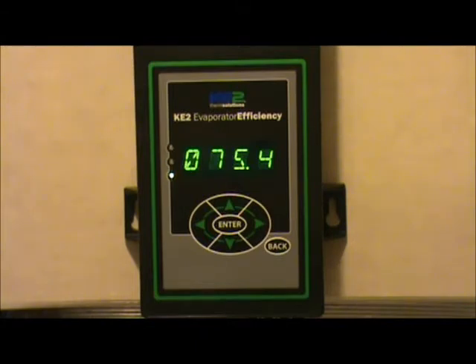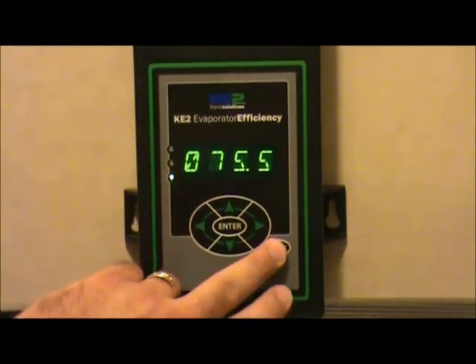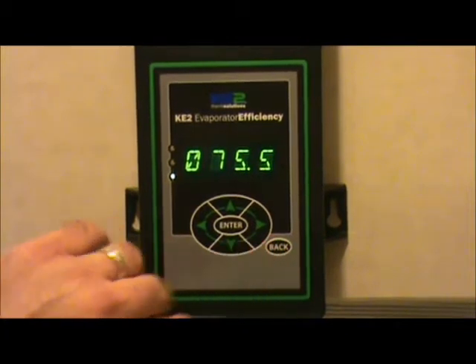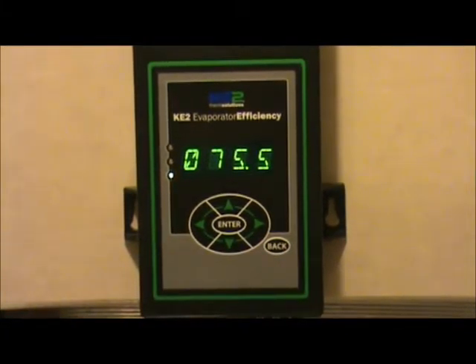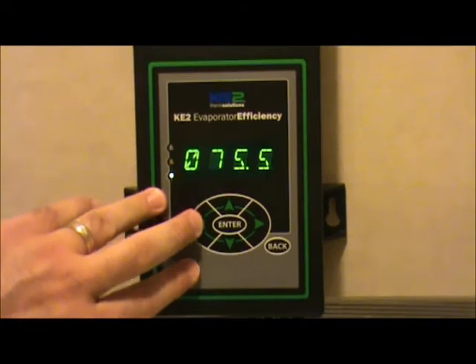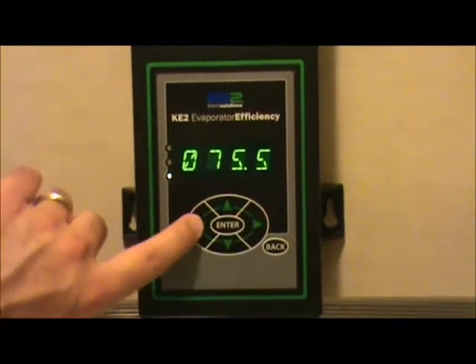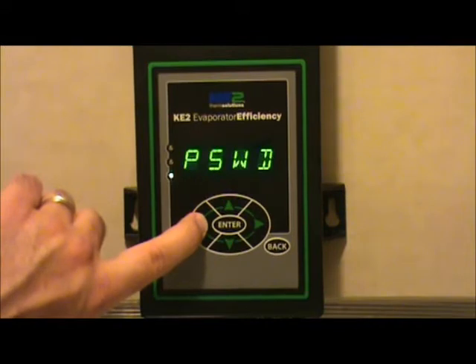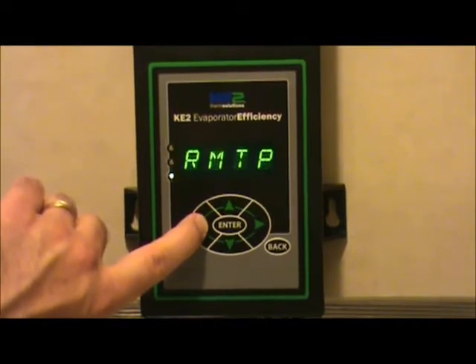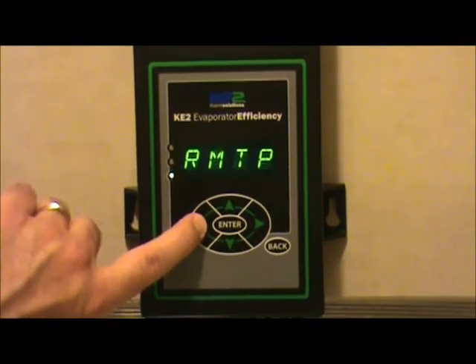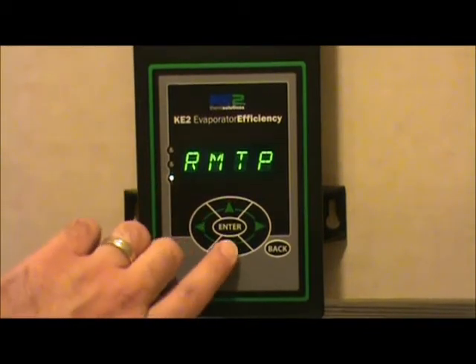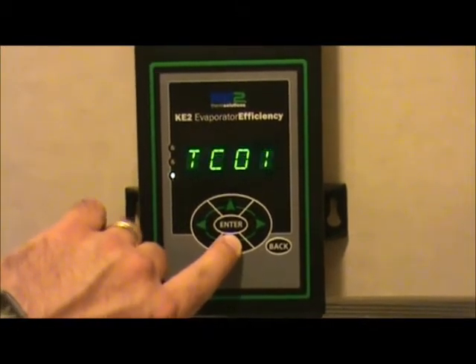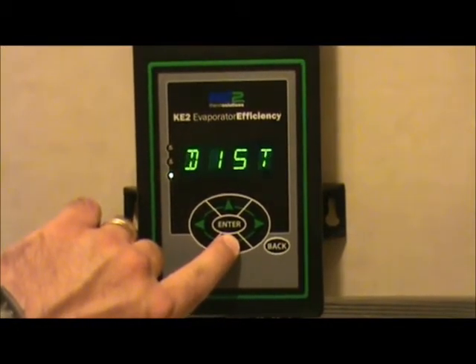To get to the variables column, you do not need a password for this application. First, press the back button a couple of times to make sure you're at the home spot, the starting point of the room temperature display. Then navigate with the left or right arrow keys to go to the top of the variables column heading, which should be RMTP. Once you see RMTP, you're at the top of the variables column, and you can scroll up and down through that entire column without needing a password to see any of these features.